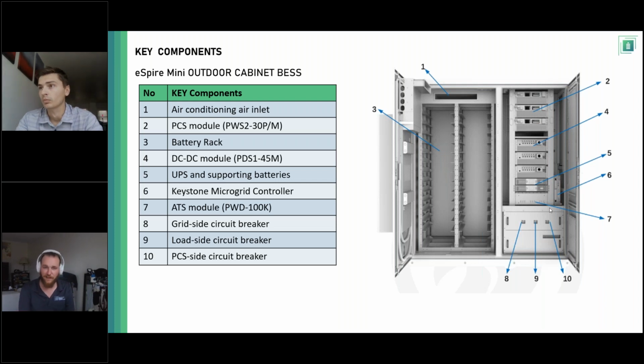Right below that are the 45 kW DC to DC modules. Each one can take in, I believe, 2 strings, so each one has 2 inputs. You can have up to 6 strings in a 135 kW cabinet when you have 3 of those DC to DC modules installed. That gives you some flexibility in how you design your solar. And again, the whole goal is to eliminate the PV inverters when we can.